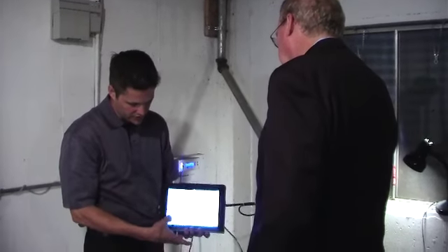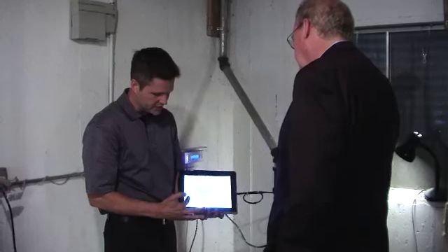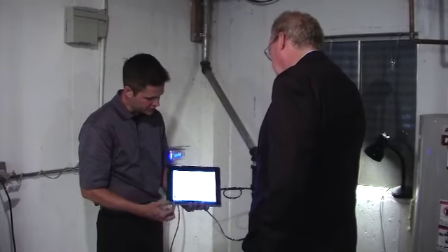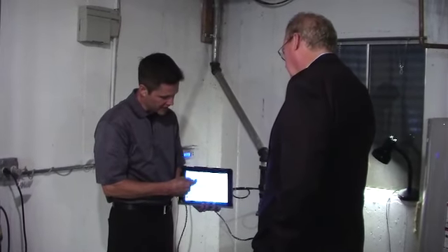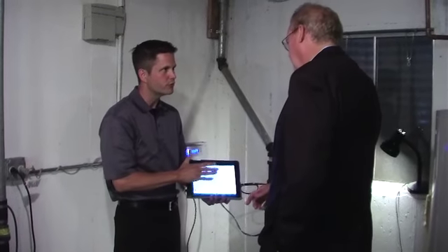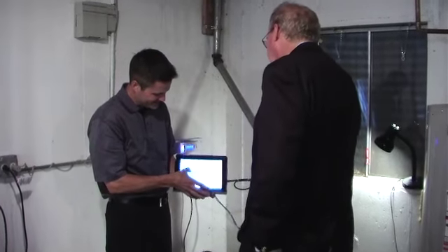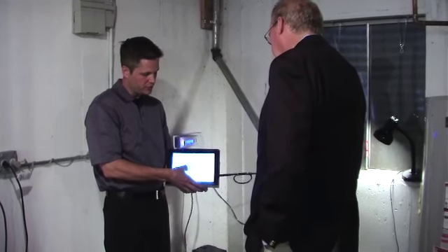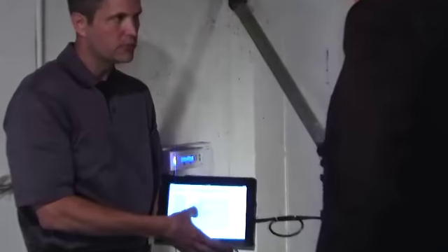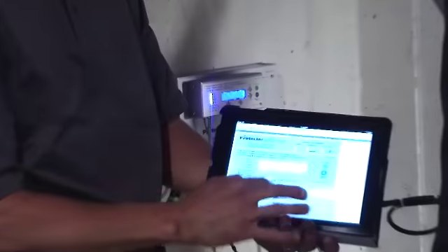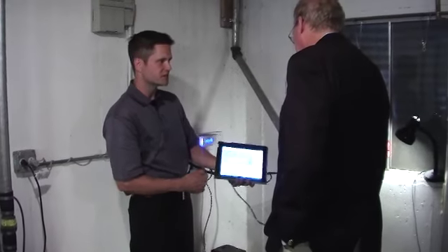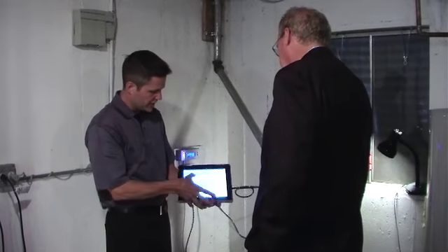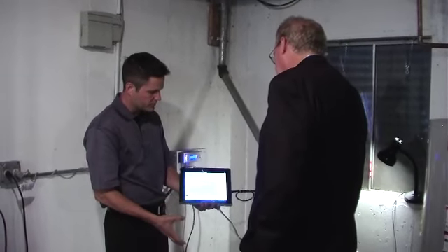So just to pick a couple of things: pump runtime is at 10 seconds. It'll self-test every 12 hours. The name is Howl. We'll white out your phone number there. Don't worry about it. And then you can run a pump test. So right here, I'm going to push a button and you'll hear the pump start running. Yeah, it's great. I'm going to turn it off. But you'll see results back up here on the screen. System 1 test successful.